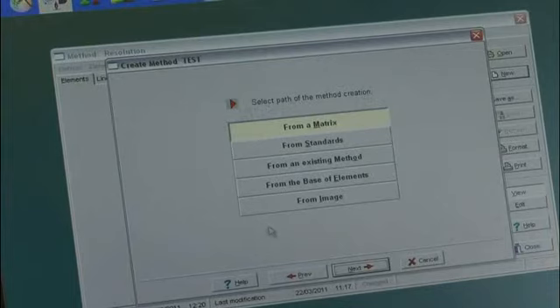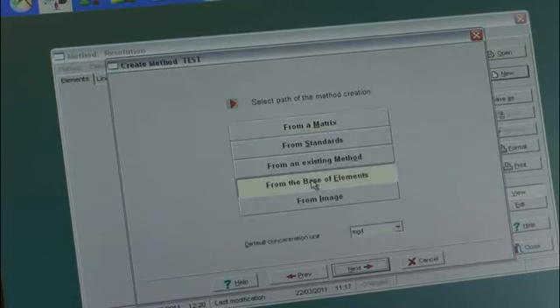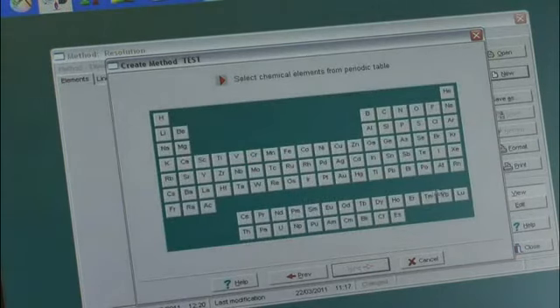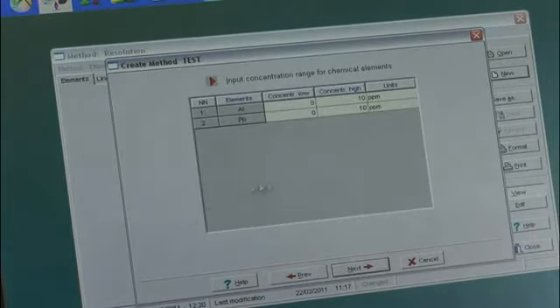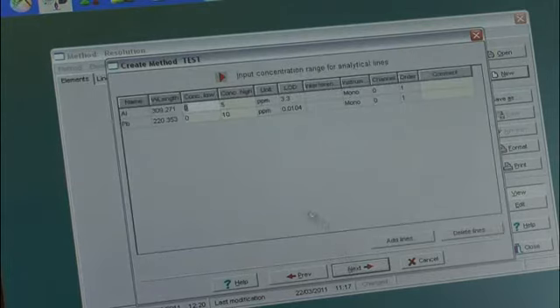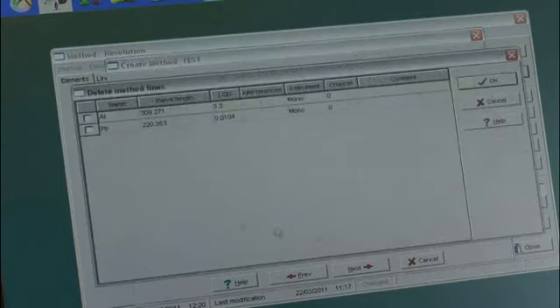And here you could either choose elements from another matrix, from standard, from another method. I'm going to say from base of elements. I'm going to say I want in ppm. Next. Here I choose what elements, so I'll say aluminum and lead. Next. This is just an information table. It's not what your standards are. So I know that aluminum is 5 and lead is 10, so I'll just leave that there. That's just the range. Here you choose what wavelengths you want to use. So I'm going to delete the 309 and I'll leave the 220.